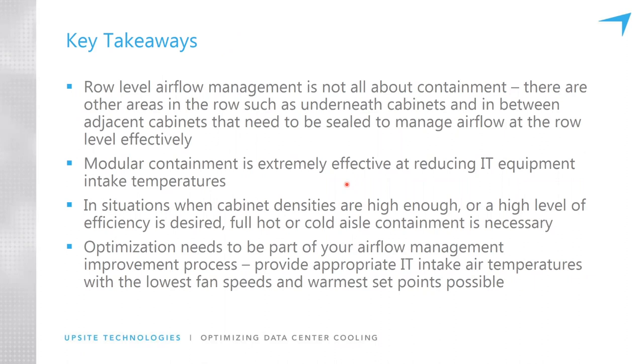So the key takeaways are row level airflow management. It's not all about containment. There's other areas in the room, in the row, that need to be addressed, underneath cabinets, between cabinets. And it's surprising and really impressive to me each time I do it, how much finishing the job, finishing that last 20, that last 10%, how much benefit you get from really finishing the job. Modular containment is really valuable. You can put in those baffles and still reduce fan speeds a great deal. Baffles, partial containment, can easily be 80, 90% of the benefits of full containment in some situations.